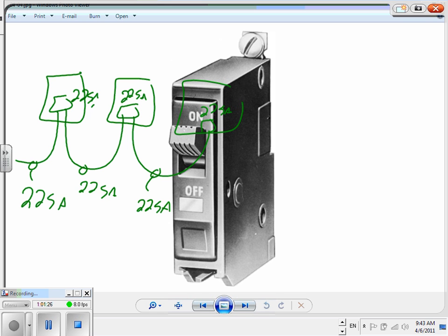And why do I put a circuit breaker here? Do I need a circuit breaker here? I don't. But if you don't put a circuit breaker here, guess what? If something happened in this panel, you lost. There's an overcurrent protection device right here, 225 amp, right in this panel. If you don't put circuit breakers on them, which you don't have to, then if you have a short circuit here or here or here, it will take the main. Do you really want that? So that's how they use the subfeed.